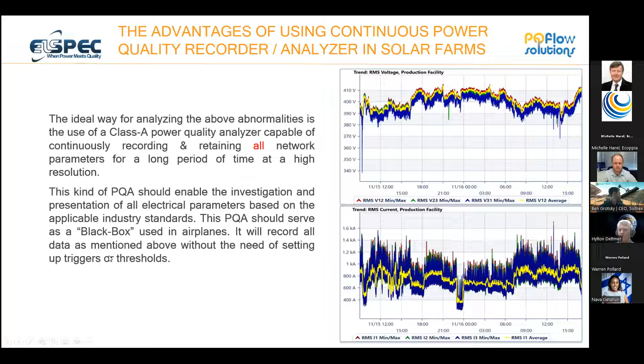In this instance, when you look at the network, this particular voltage profile shows a step change - there was a tap change on the network - but this is over 1850 cycles. If you were to take an average of that, you would never see the step change in this network because the average would not see it as an event. So on average, you'd just see a slight change in the voltage profile without understanding that it's actually a tap changer that brought this about.